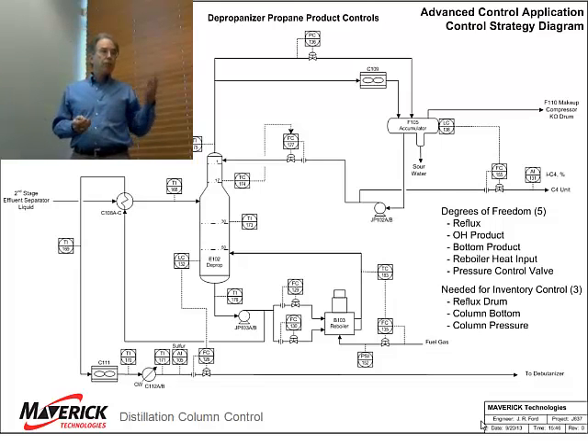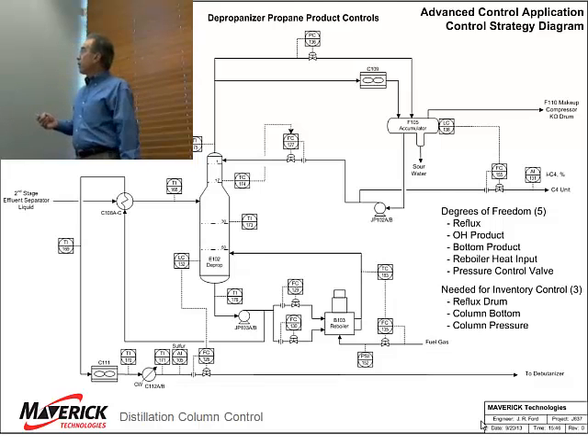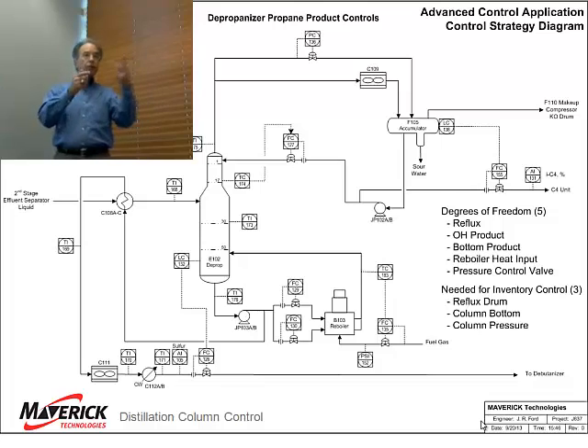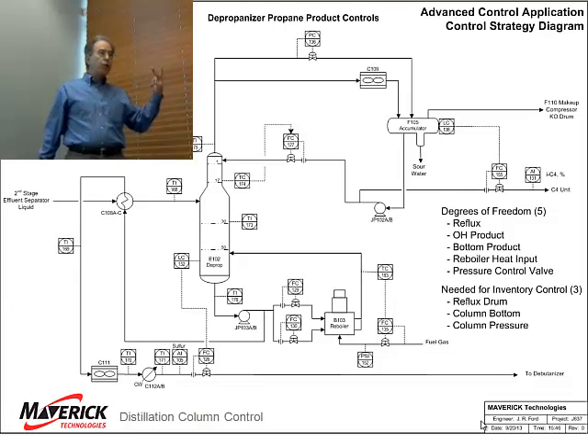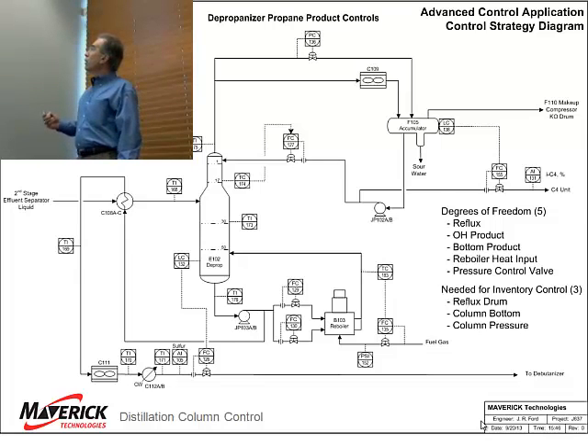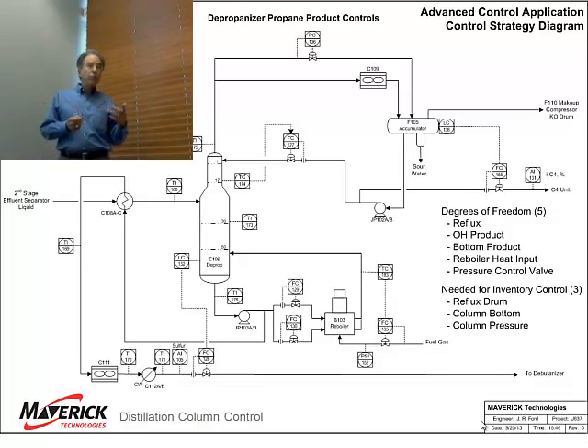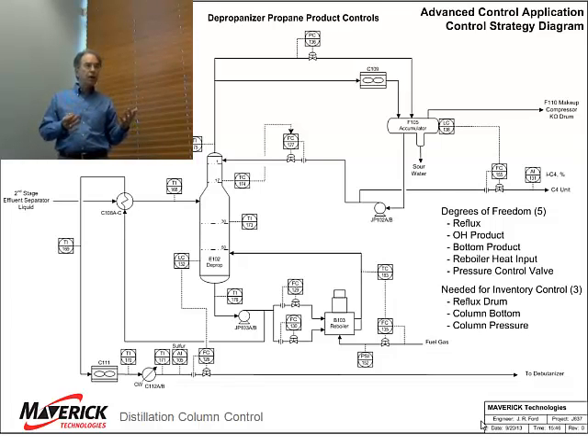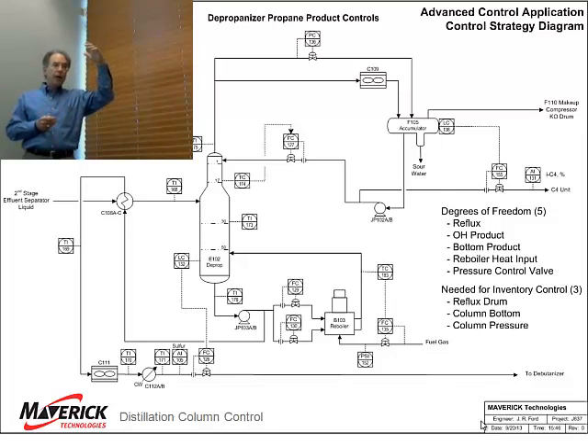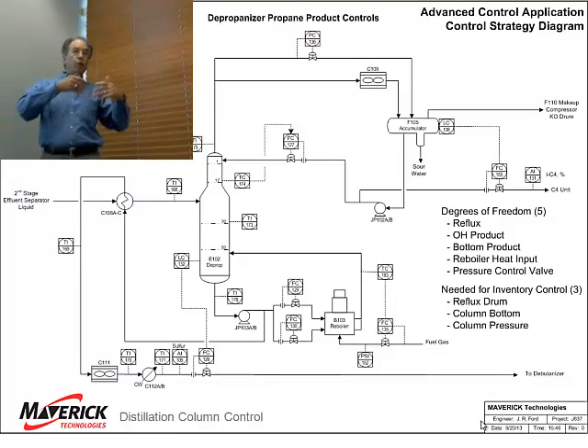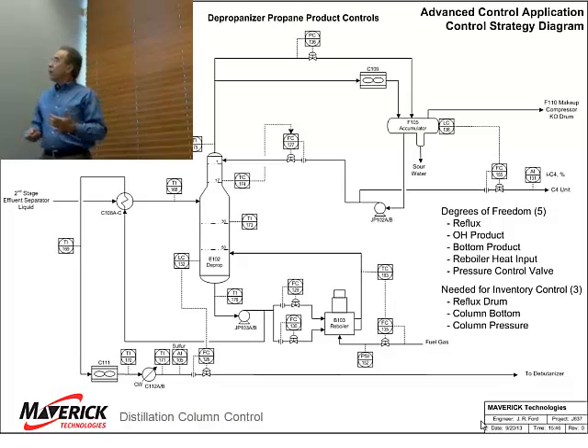In a typical distillation column you've got two degrees of freedom left, and those are typically the reflux and the reboiler heat input. With two independent manipulated variables you can control two things. You could say why not control the overhead product composition and bottom product composition? Theoretically that's nice, but in reality it's hard because controlling both compositions requires a unique solution of the energy and material balance. So we'll typically control one product composition tight and maybe control a separation variable like a reflux-to-feed ratio.